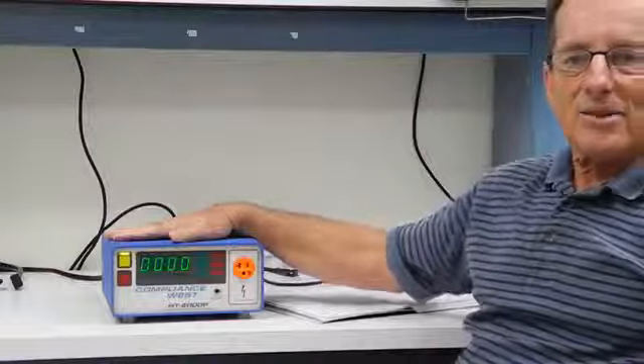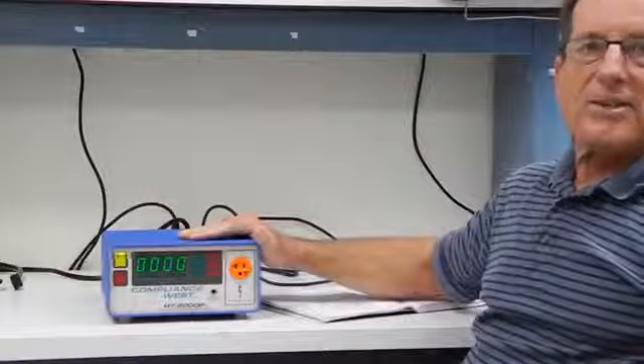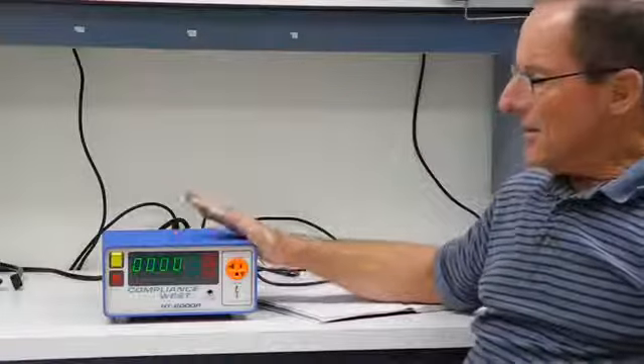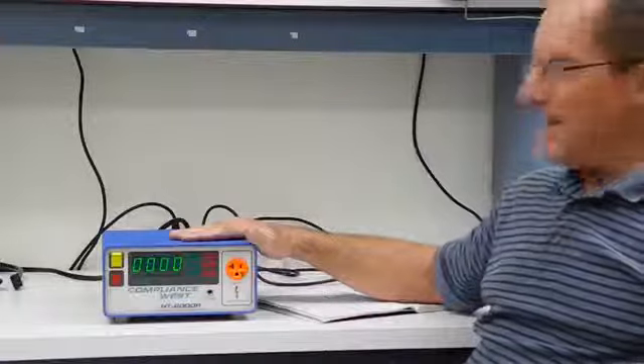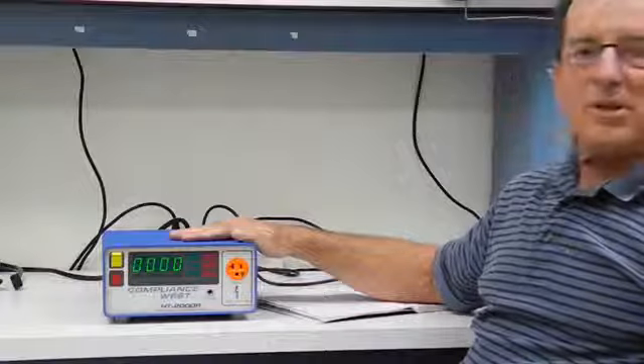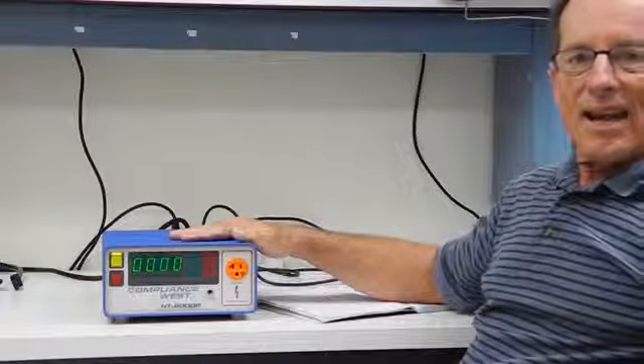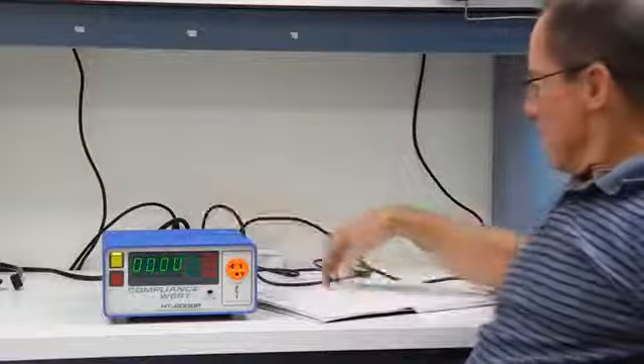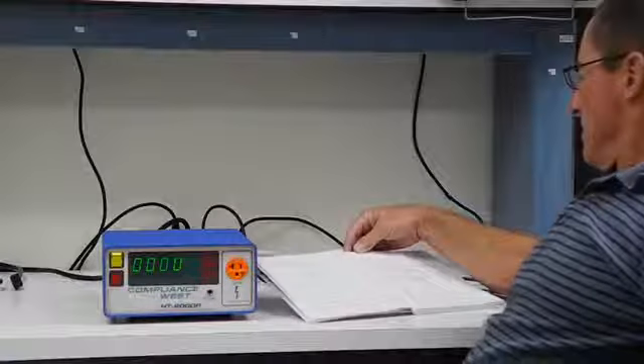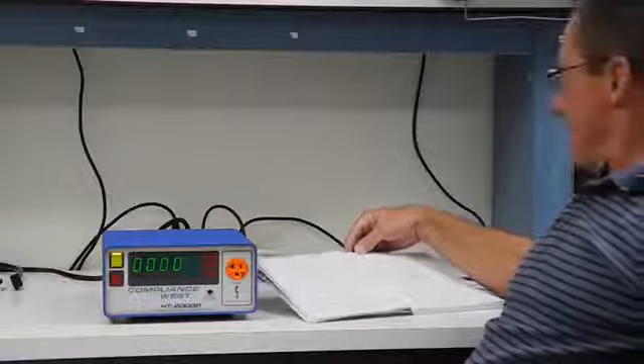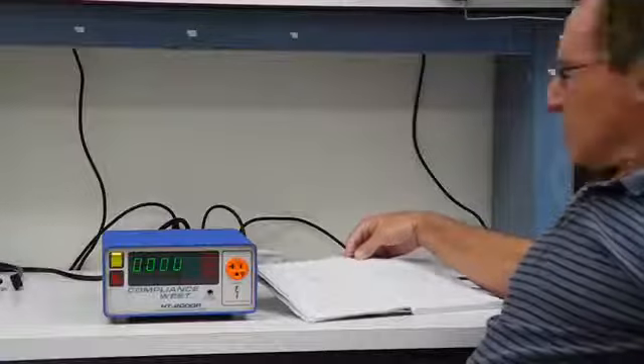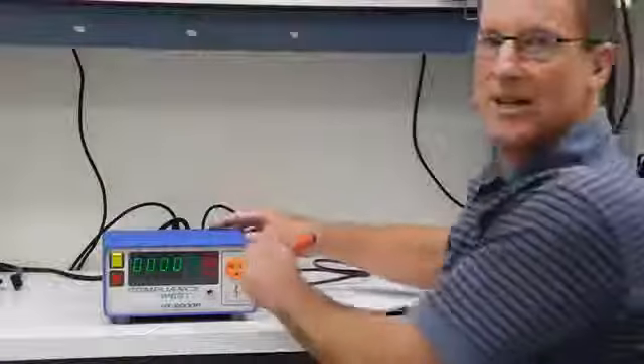Today I'm just going to run through real quickly how to conduct a test and do the adjustments of an HT-2000P high pot tester. This high pot tester outputs AC and up to 2,000 volts. Today I'm going to show you how to configure it for 1200 volts AC, trip current of 2 mils, and a test time of 1 second. That's all done on the back panel.